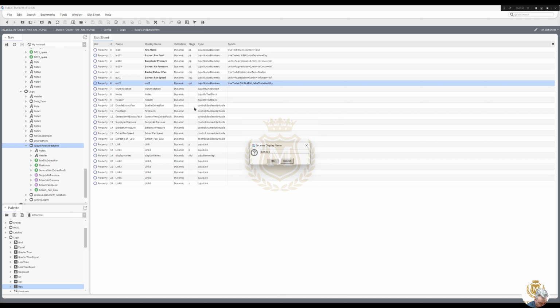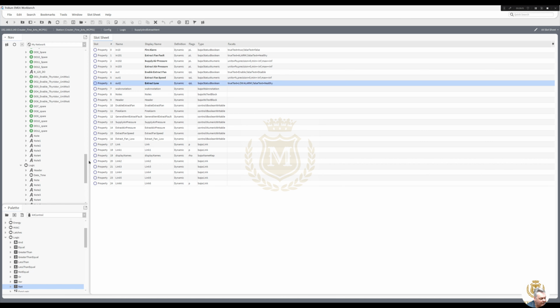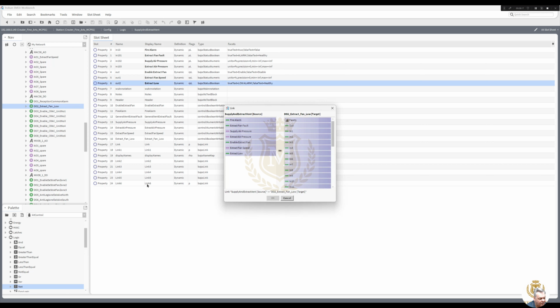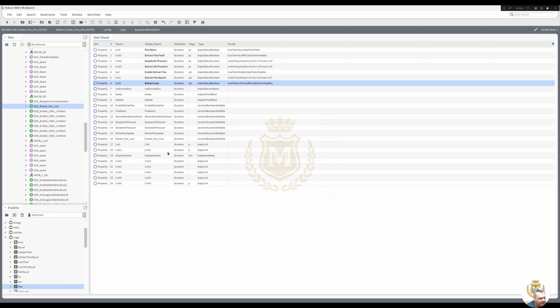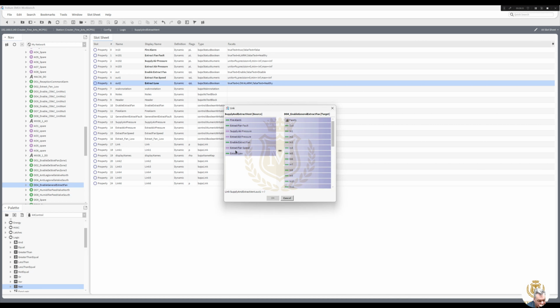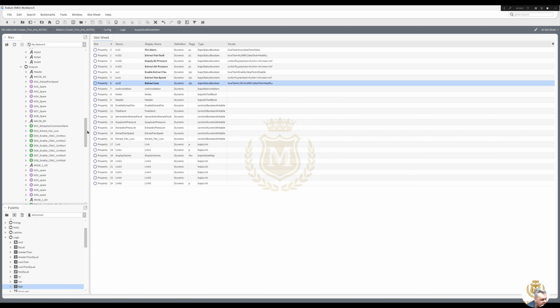Extract low, link mark that. Now we can put the outputs in there, and I can find it again. Extract fan low, link from extract low into in10 of the digital output. We've got an enable, link from enable into the output, and then we've got a speed, link from fan speed into the analog output.